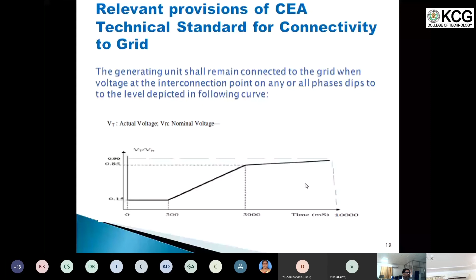Also, photovoltaic generation or renewable generation is required to be able to vary the reactive power from 0.95 lagging to 0.95 leading. Now, this can be done, and this is being done, but an issue for the developers is that the rating they provide for the inverter is typically in terms of the MVA rating, for whatever active power output you are looking for. If you are operating that inverter at 0.95 lagging or a power factor other than unity, then your capacity to transmit real power will reduce, and you will have to curtail the real power if required.